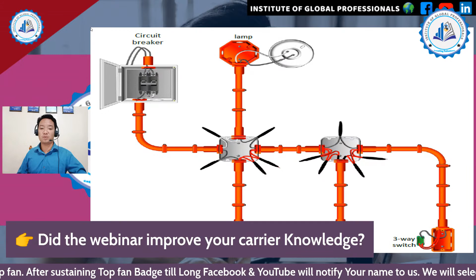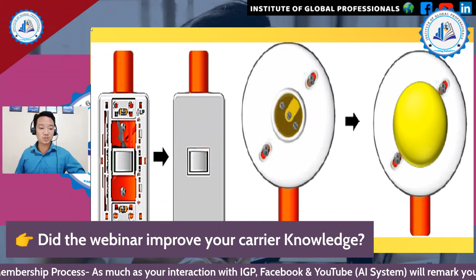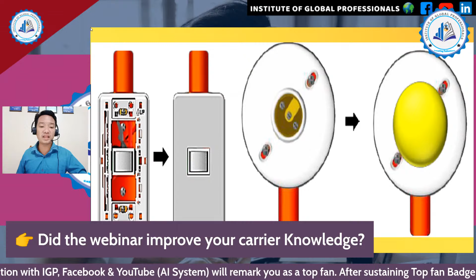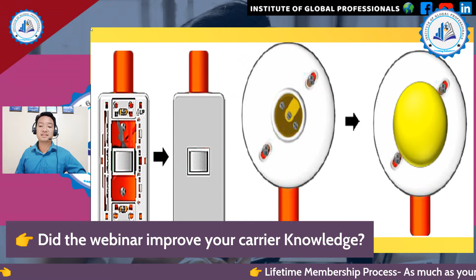Step 13: screw the fixtures to their utility boxes or junction boxes. The next picture shows how to fix the fixture after terminations and testing the circuit, including how to terminate the switch and finalize it by installing the faceplate of the switch. As you can see, in four-way and three-way switches there is no on or off symbol, and they should be attached with screws. Likewise, receptacles or lamp holders should be attached properly to avoid malfunctioning.